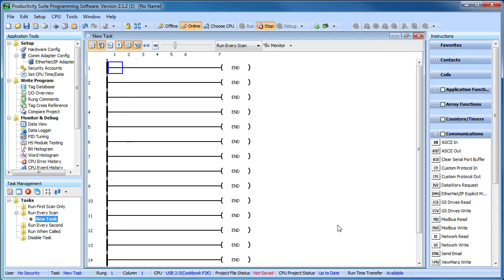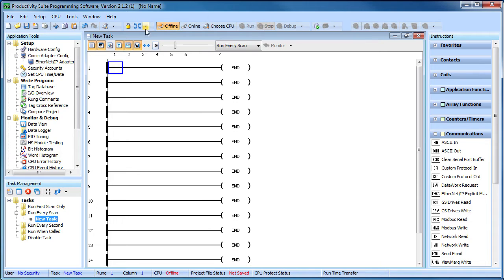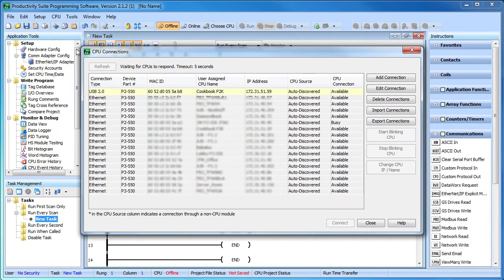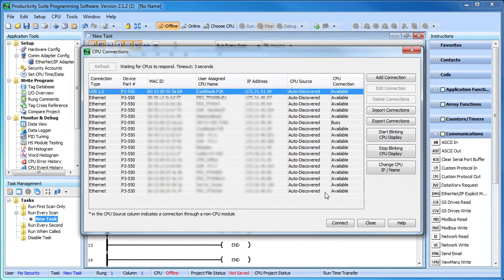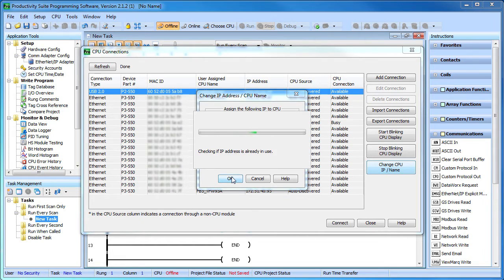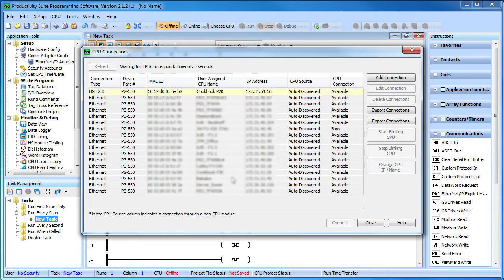To change the IP address so it is compatible with that network, make sure you are offline and go to CPU, choose CPU, highlight this controller and change the CPU address. Just like before, the Productivity Suite software validates that IP address and you are ready to go.